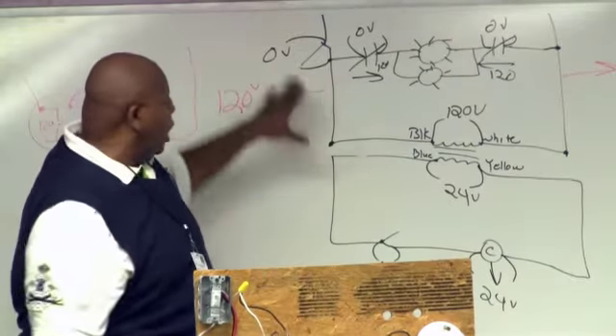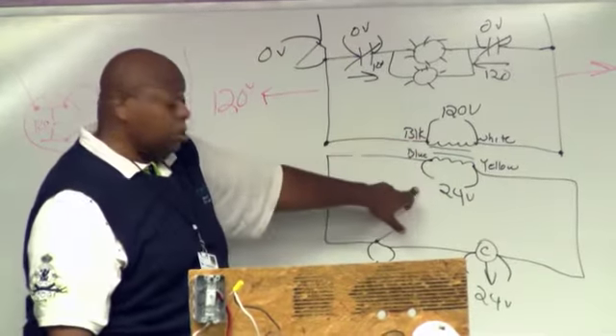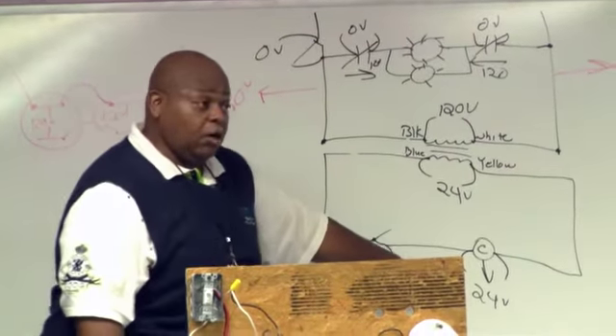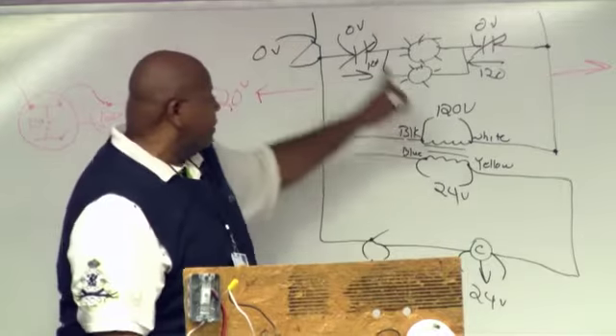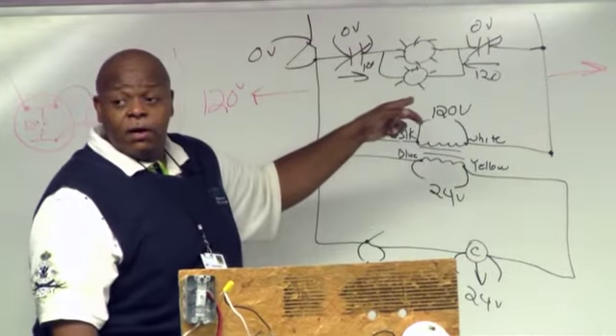So, that's how you troubleshoot. You start with your main power, go to your transformer, go to your low voltage, to your switch, to the coil, because the coil has to energize to make the contacts close. Follow me, any questions so far?